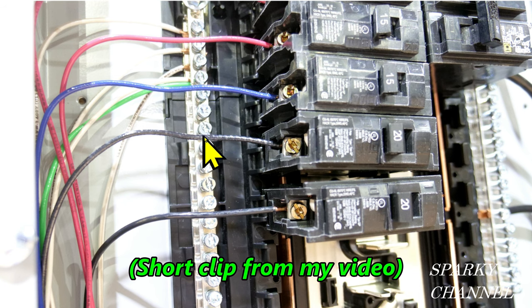This 14 gauge wire is going to a 20 amp circuit breaker. Now that's not correct. A 20 amp circuit breaker should have the thicker wire. You see how this is thicker than the other three? This is 12 gauge wire. Okay, so this is incorrect. We've got a 14 gauge wire going to a 20 amp circuit breaker. So this is a code violation right here. And the other thing is that this circuit breaker appears to be rather loose. Check to make sure that it's installed properly.